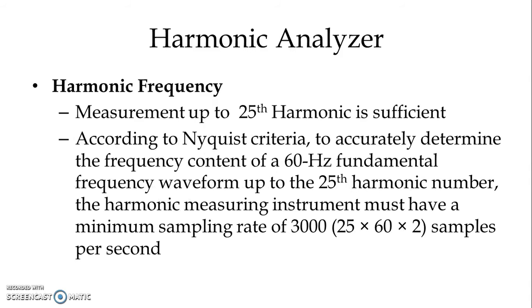According to the Nyquist criteria, to accurately determine the frequency content of a 60 Hz fundamental frequency waveform up to the 25th harmonic, the harmonic measuring instrument must have a minimum sampling rate of 3000 samples per second. That is the 25th harmonic multiplied by 60 Hz fundamental frequency, doubled — giving 3000 samples per second.